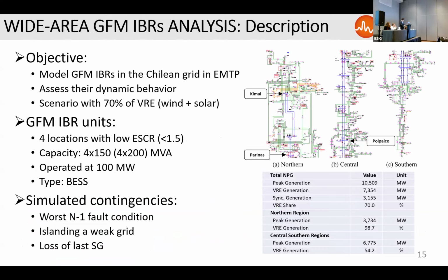Right, so what was the objective of the study? It is to model grid forming converters in the grid and assess their dynamic behavior in the case of a very high level of renewable generation, 70% in particular. So they installed GFM converters in 4 locations with very low short circuit ratio, the points where they need the most support. And the contingencies that were studied are basically 3: the worst N-1 fault, islanding, and the loss of the last synchronous generator, so they are only operating with converters in the island.